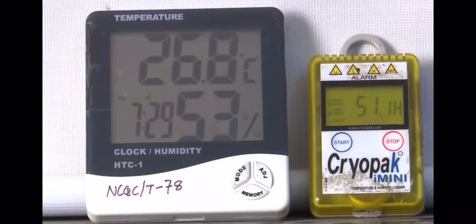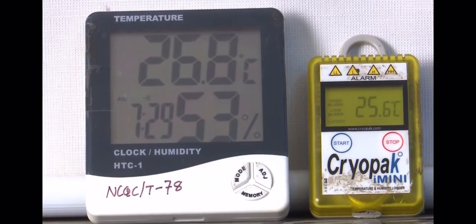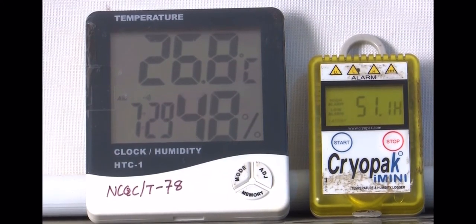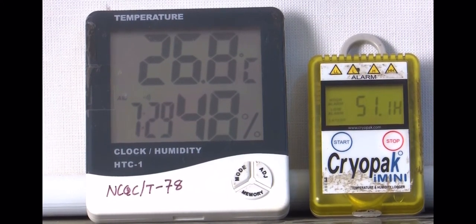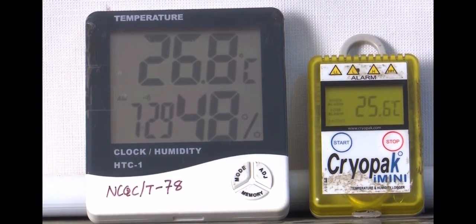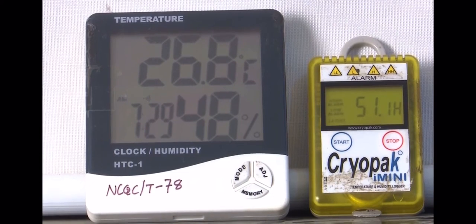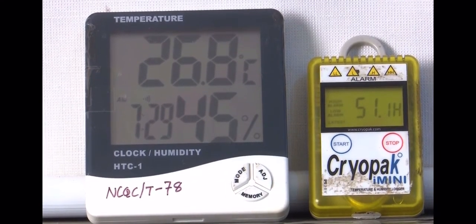Keep the digital thermohygrometer for at least 30 minutes for soaking at 25 plus minus 3 degrees centigrade so that the temperature is brought to equilibrium. Before starting calibration, ensure that the environment condition is maintained. The temperature should be between 25 plus minus 3 degrees centigrade and humidity should be 45 to 75% RH.